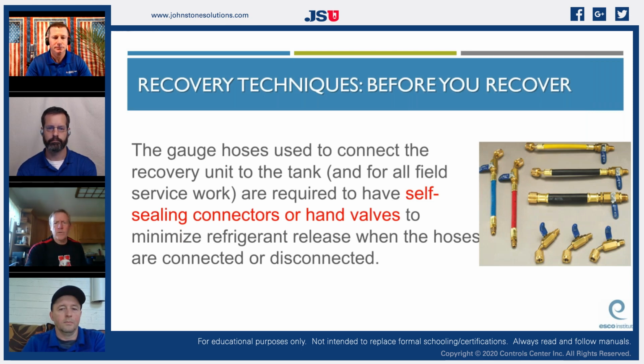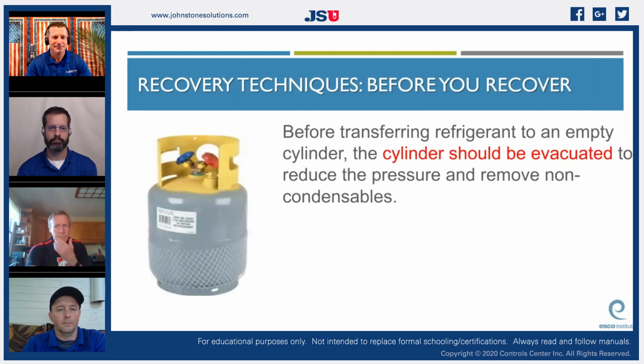We also taught our guys in the field a practice of taking the high side off while it was running with those particular fittings in there, and then throttling your gauges to push that liquid back into the system, especially in a critically charged application, so that you're not removing 3 to 4 ounces every time you take your gauges off. It's a technique we taught especially when we started going to microchannel, critical charge heat pumps and stuff like that. If you're servicing it twice a year, you could be removing 1/3 of a pound every year. Then in a couple years, you're looking for a leak that doesn't exist. Exactly. Try to use some good practices when it comes to removing your gauges.